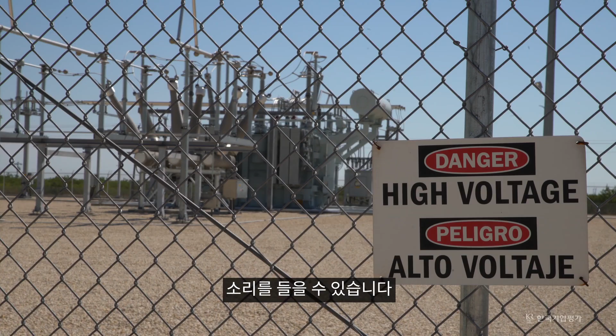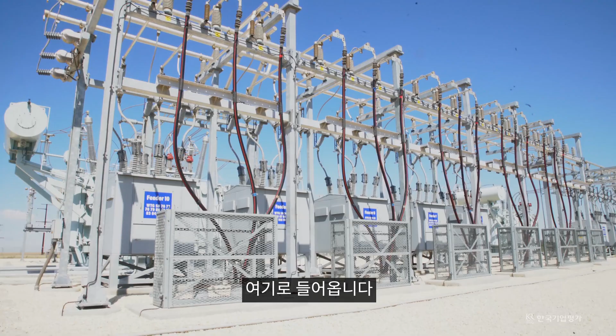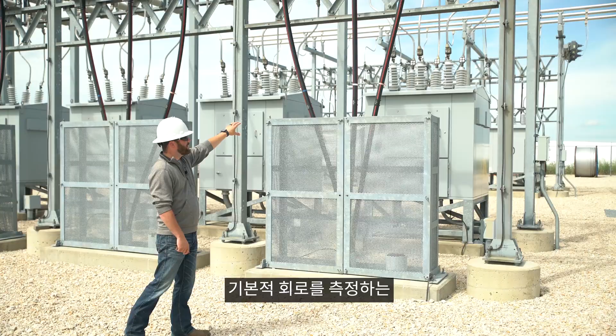This is where all our turbine collection comes in. The turbine out in the field produces electricity, which comes underground and collects into the substation yard. It goes into a circuit breaker, which meters the circuit. If a fault occurs within a turbine, that breaker opens and disconnects the rest of the substation from that feeder—like the breakers in a junction box at your house, just on a much larger scale.